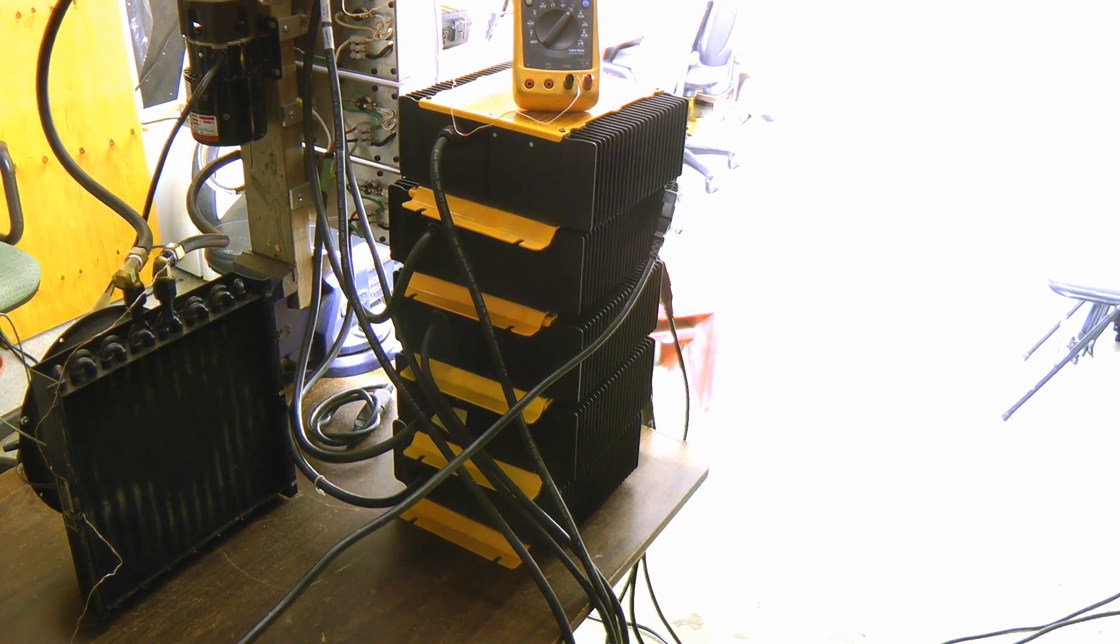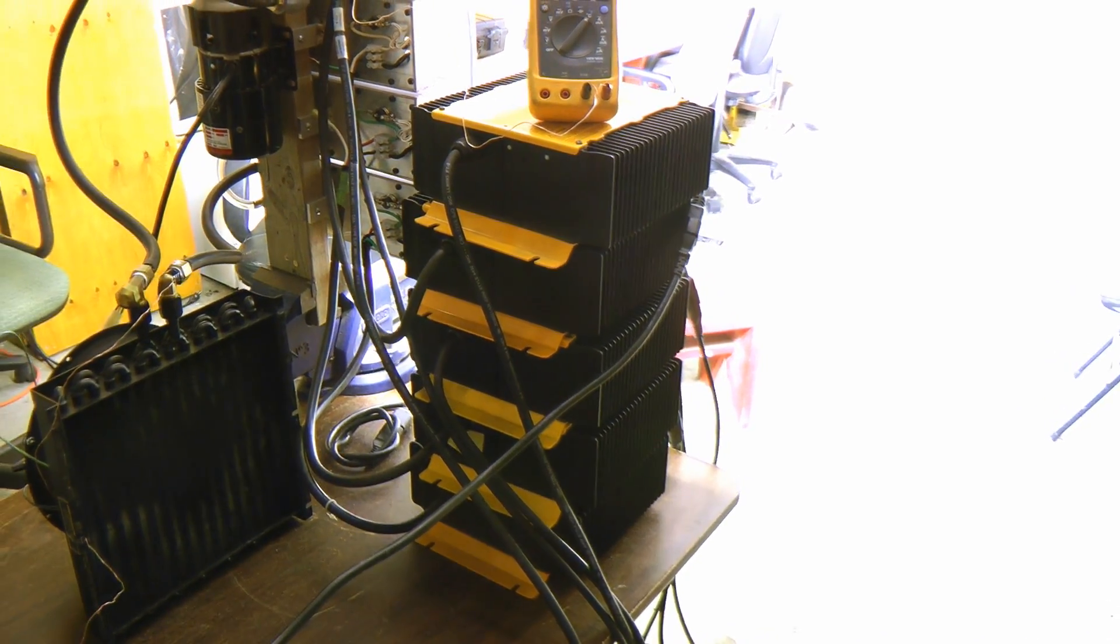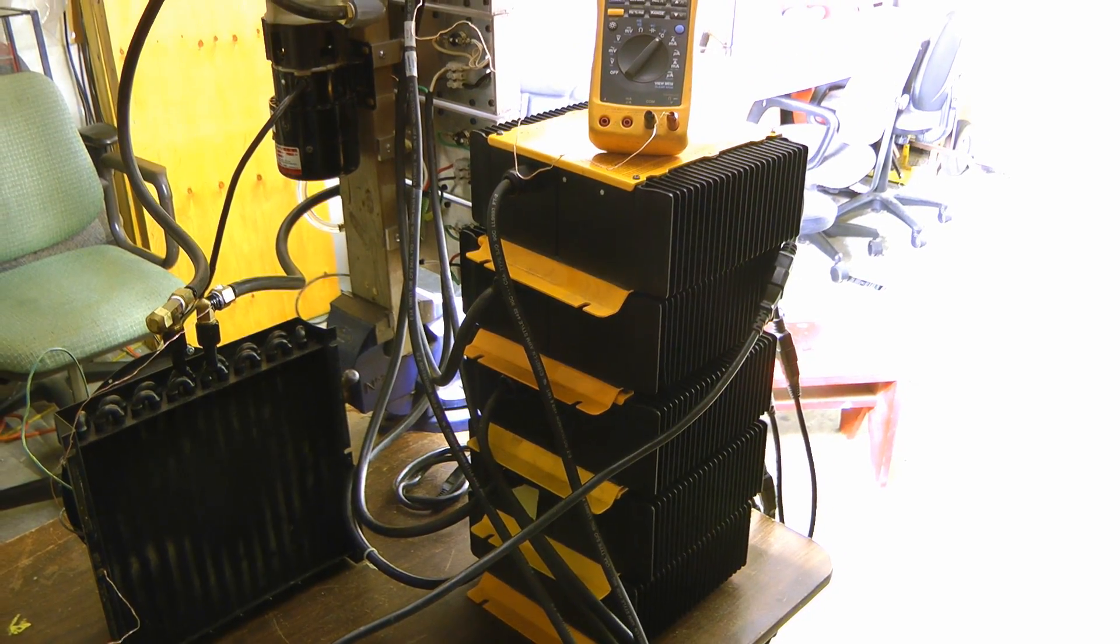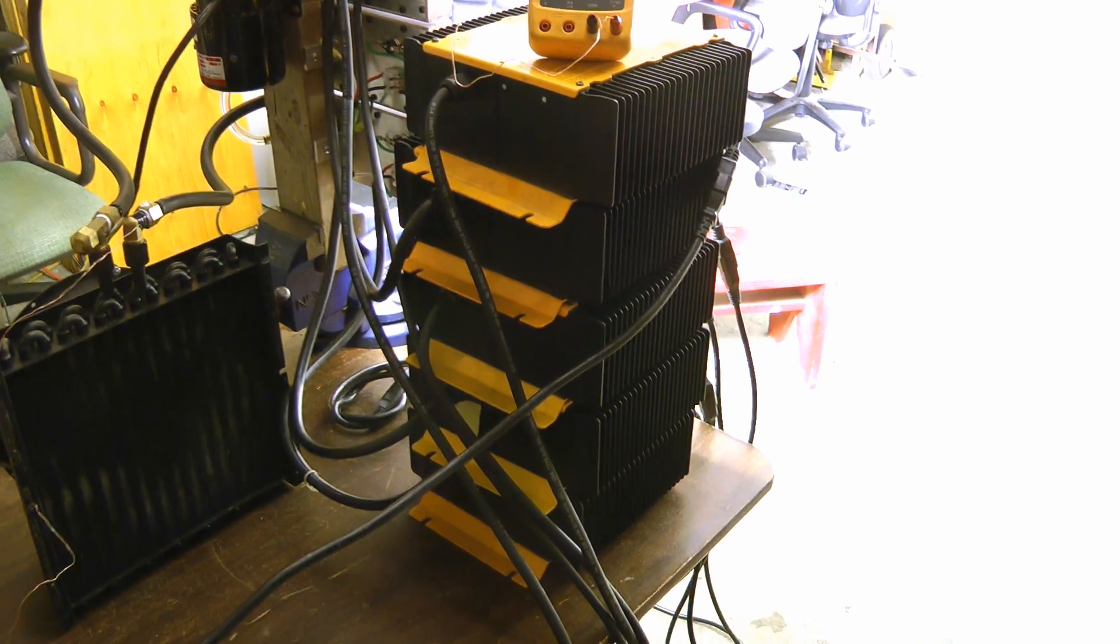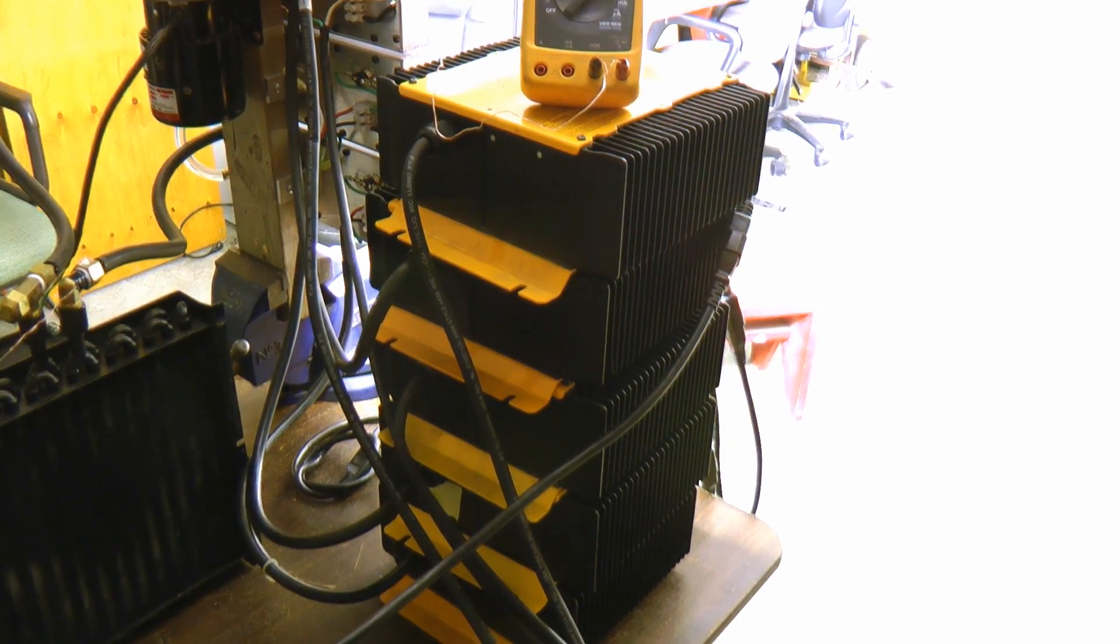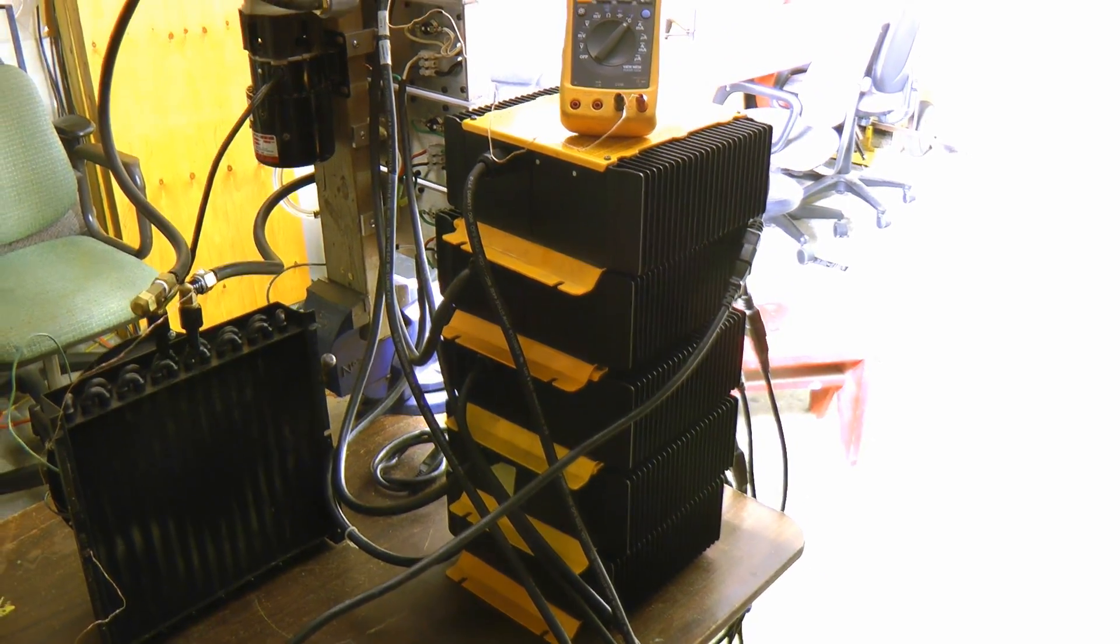The modules are powered by these modified Delta Q golf cart battery chargers. These are supplying 18 amps at about 60 volts to each module.